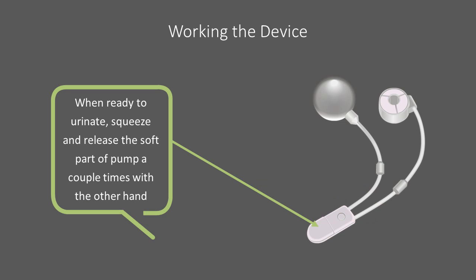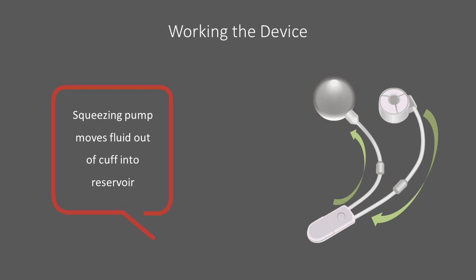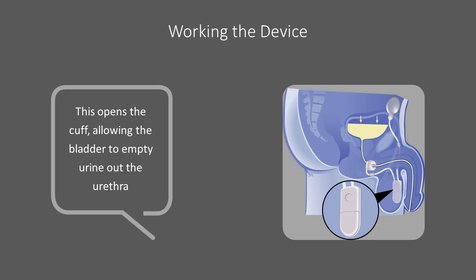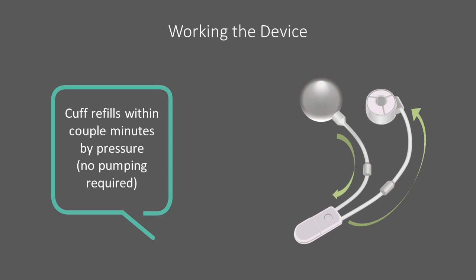Again, when ready to urinate, squeeze and release the soft part of the pump a couple times with the other hand. Squeezing the pump moves fluid out of the cuff and temporarily into the pressure-regulating reservoir balloon. This opens the cuff temporarily, allowing the bladder to empty urine out of the urethra. After urinating, the cuff refills within a couple minutes by pressure. No action on your part is required.